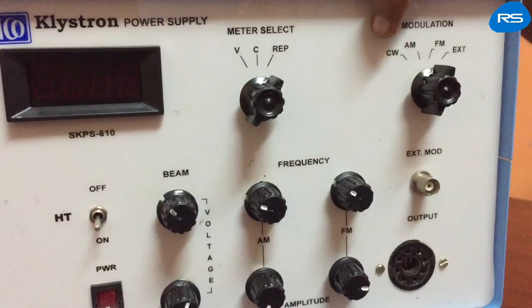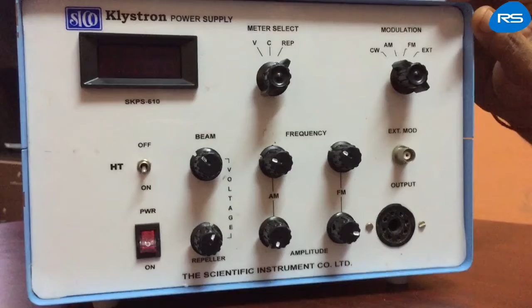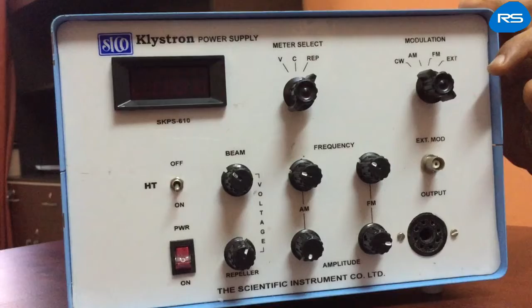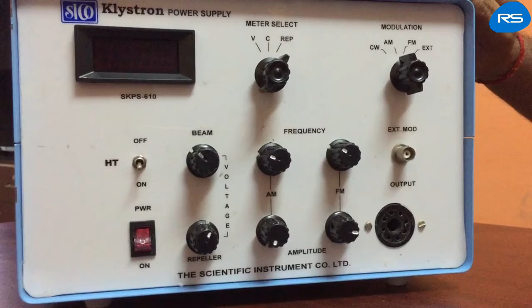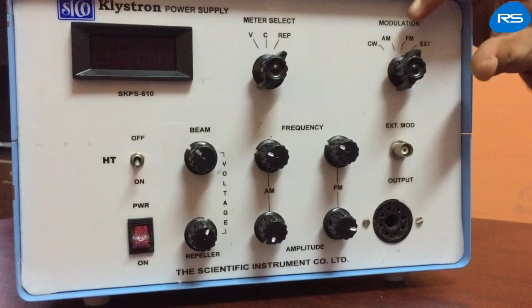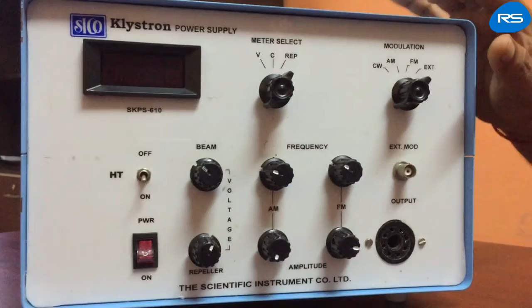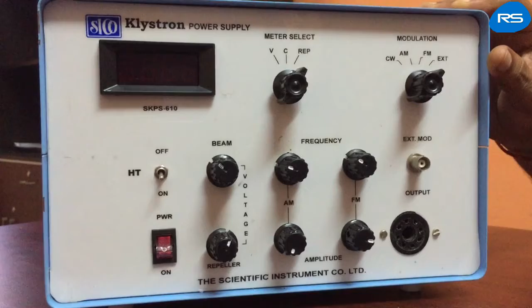Modulation. CW position: modulation is not applied and the Klystron operates at carrier wave. HV of the internal modulator circuit is switched off to reduce hum pickup. AM position: square wave modulation is switched on and is applied to the reflector of the reflex Klystron tube. FM position: sawtooth modulation is switched on. External position: internal modulation is switched off and an external modulator can be applied through the BNC connector of the panel.